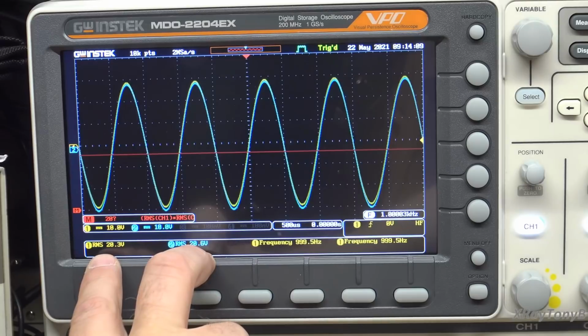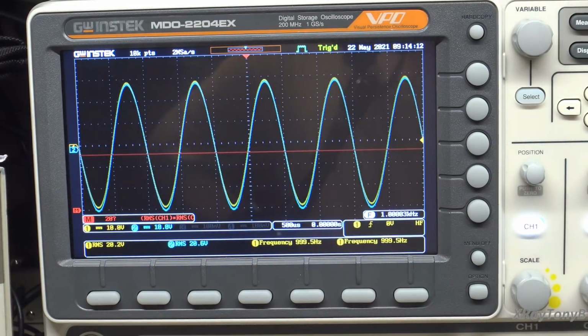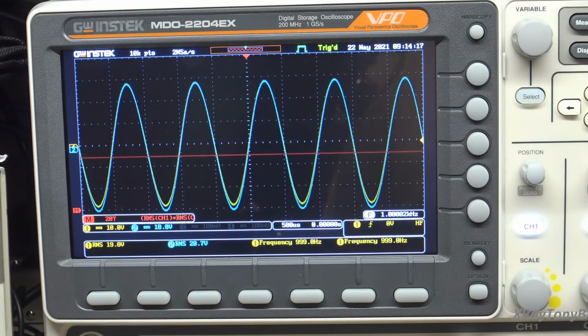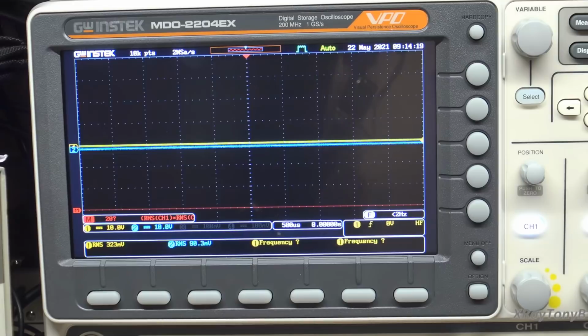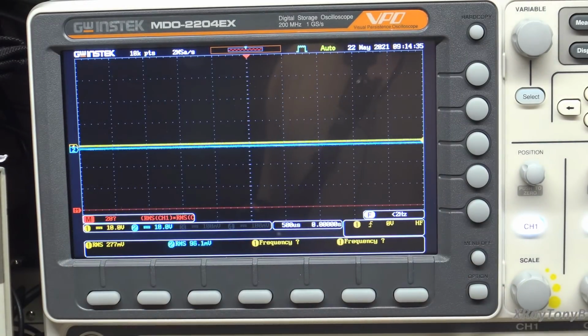By the way, the RMS voltage that we're using to calculate the wattage, that's where a lot of people will say RMS watts. It's not a true expression to say that, okay? There is no such thing as watts RMS. Wattage is a measurement of the amount of energy dissipated, okay? So when we're looking at what we're measuring now, we're looking at the amount of energy being dissipated as heat into the resistive dummy load. And we express that as watts, which is the volts times the amps.